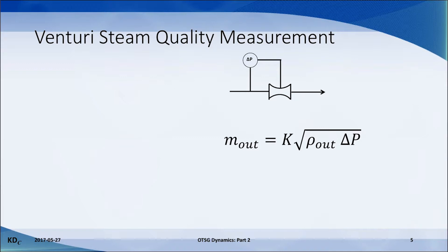But with the OTSG, we have an accurate measurement of the water flow rate into the tube, and we know the venturi pressure drop. So we flip the venturi equation around and we get an expression for the density of the outlet fluid. Then we can go to the steam tables and find the steam quality that matches this density.